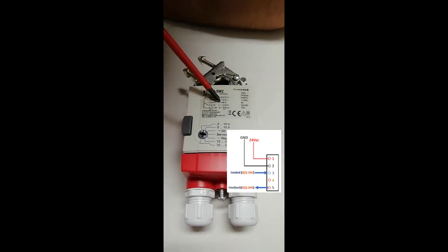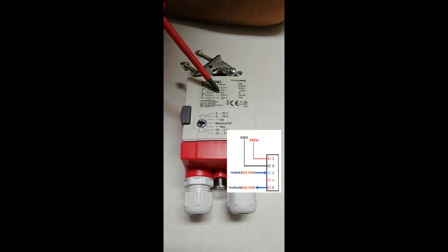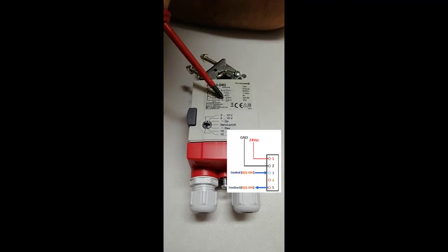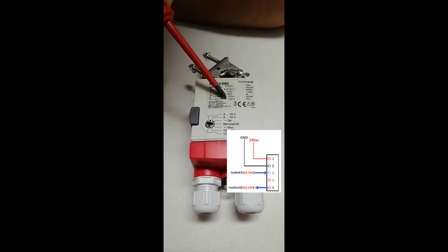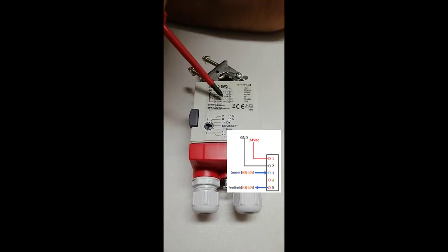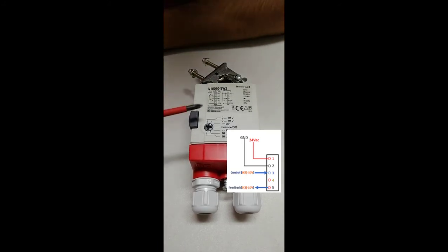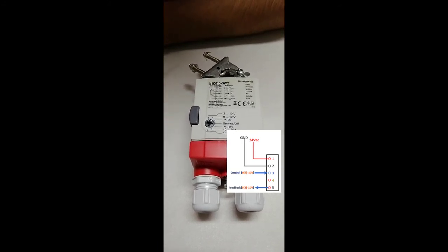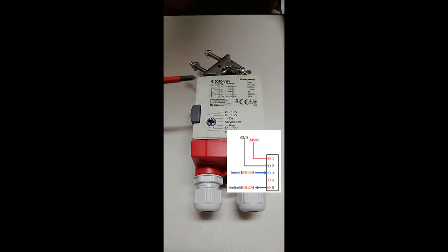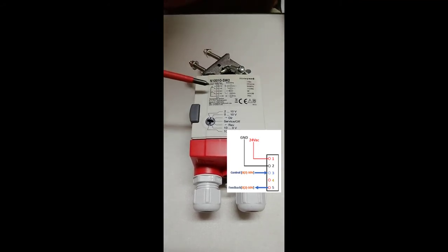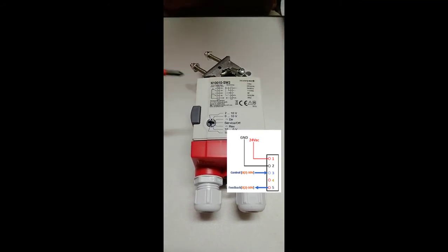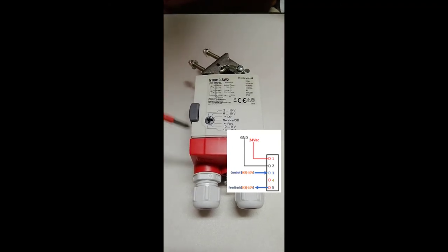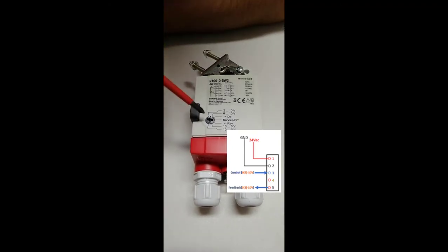On number 3, our 0 to 10 volt signal from the DDC controller is connected, and on number 5 we can take feedback for this damper. It will provide us 0 to 100% feedback of the position of this damper actuator. Then we also have end switches, as I informed you earlier in the two position control. It also has two end switches installed.